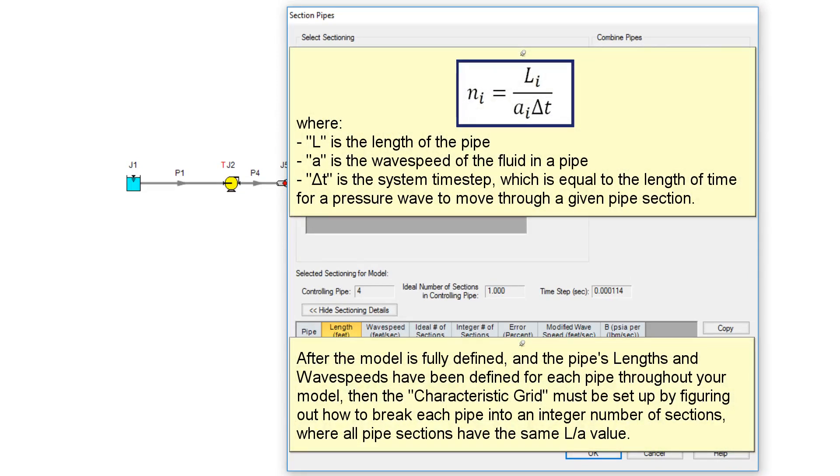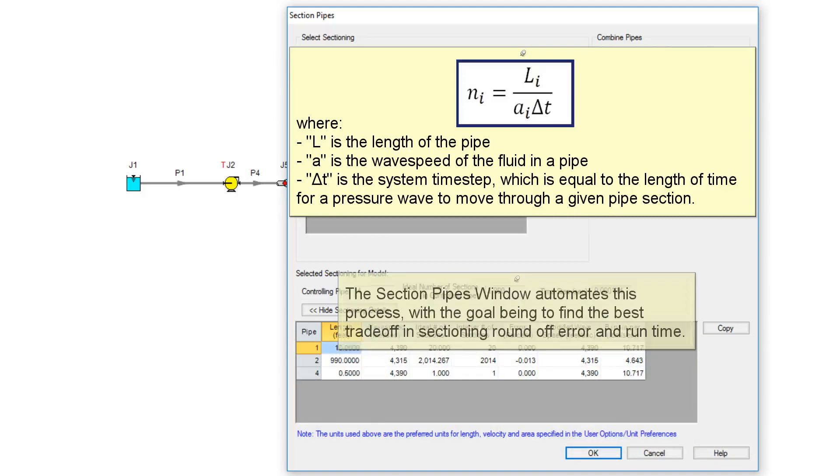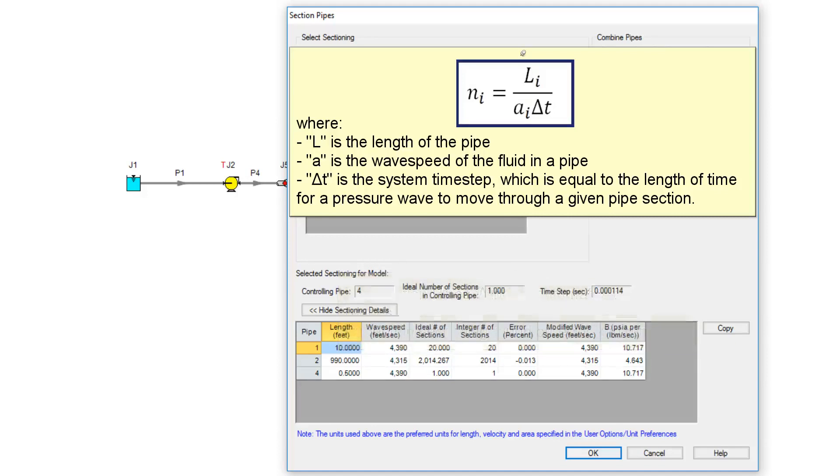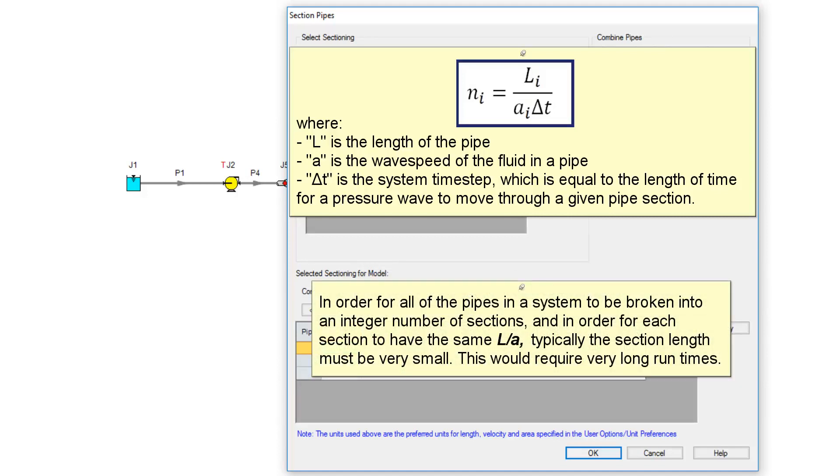After the model is fully defined, and the pipe lengths and wave speeds have been defined for each pipe throughout your model, then the characteristic grid must be set up by figuring out how to break each pipe into an integer number of sections where all pipe sections have the same L over A value. The section pipes window automates this process with the goal being to find the best trade-off in sectioning round-off error and runtime.